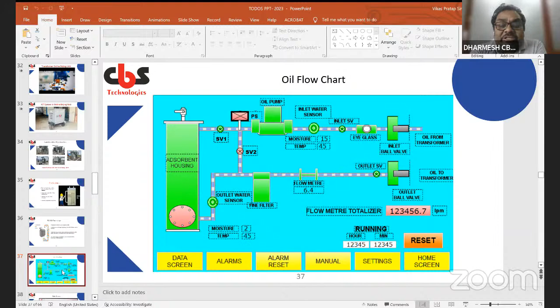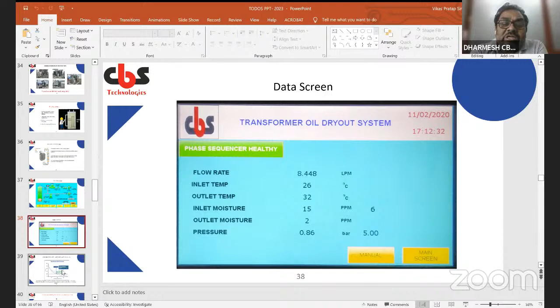Next, here you can see the flow rate is 8.448, with the inlet temperature, inlet moisture and outlet moisture shown. The inlet moisture when we put the machine is 15, and the outlet is 2 ppm. We consider the cartridge saturated once the inlet moisture and outlet moisture ppm become the same.